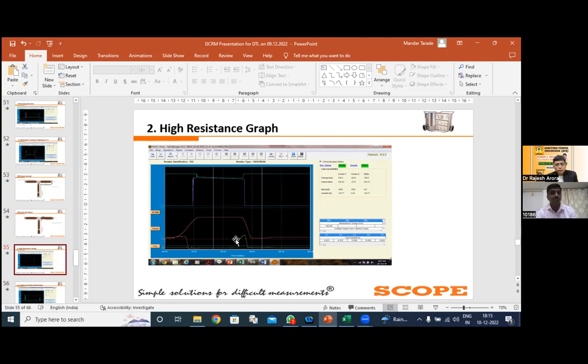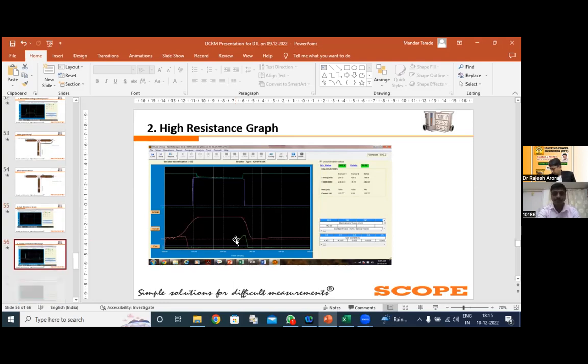If your resistance value is still on the higher side in spite of all these things, then you need to compare this DCRM resistance value with the static contact resistance value. If both the values are on the higher side, then you need to discuss with the original equipment manufacturer and take their opinion on the values.